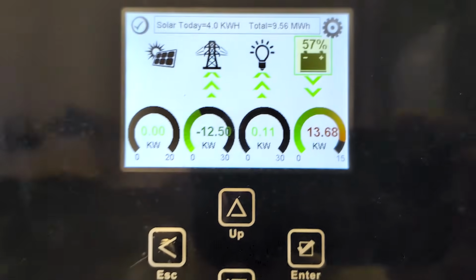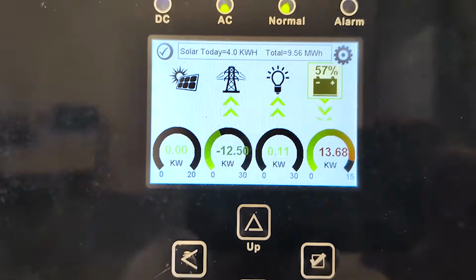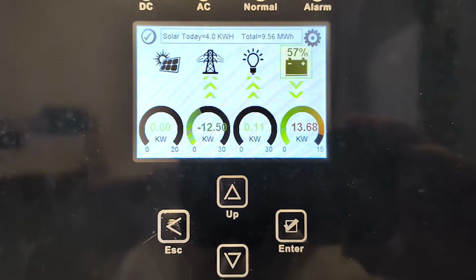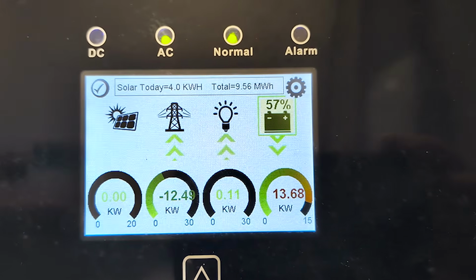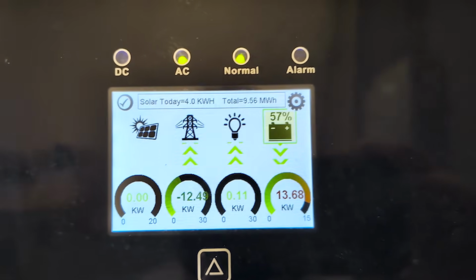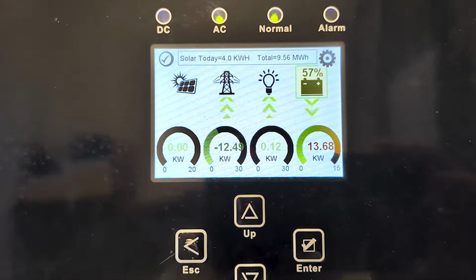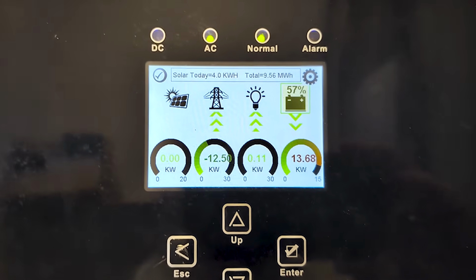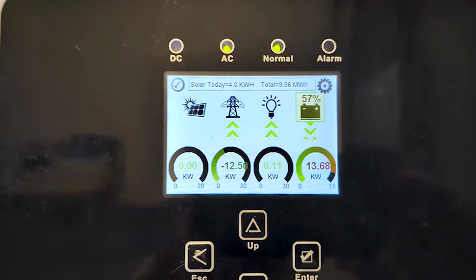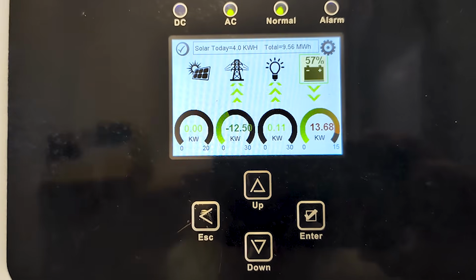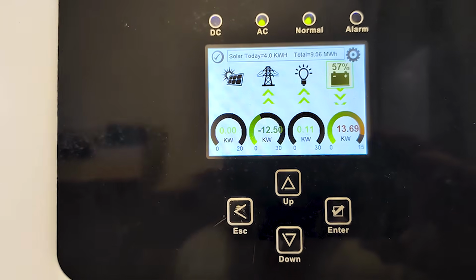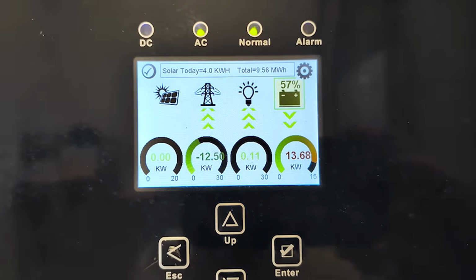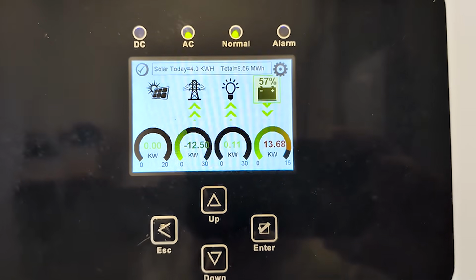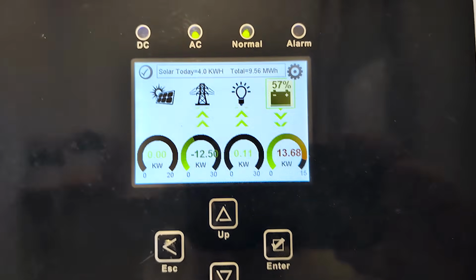Okay, we're at an hour and a half running at 12.5 kilowatts off a battery only, just dumping that battery. A nice constant load, 12.49. I should run it up to 13K and see what it does, but the spec sheet says 12K. So here's an hour and a half into it, just dumping my battery. I've dumped almost 50% of the battery out. Started at 100, now at 57%.